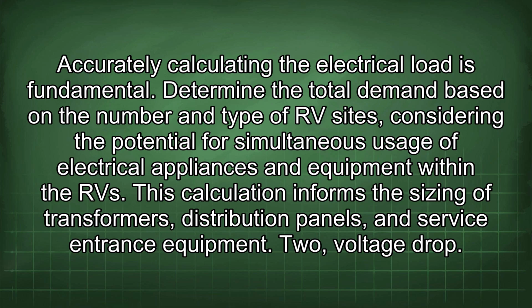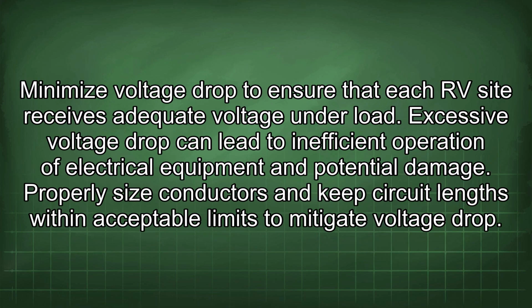2. Voltage drop. Minimize voltage drop to ensure that each RV site receives adequate voltage under load. Excessive voltage drop can lead to inefficient operation of electrical equipment and potential damage. Properly size conductors and keep circuit lengths within acceptable limits to mitigate voltage drop.